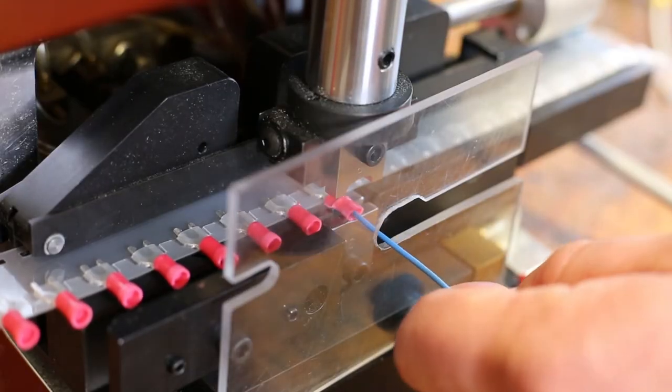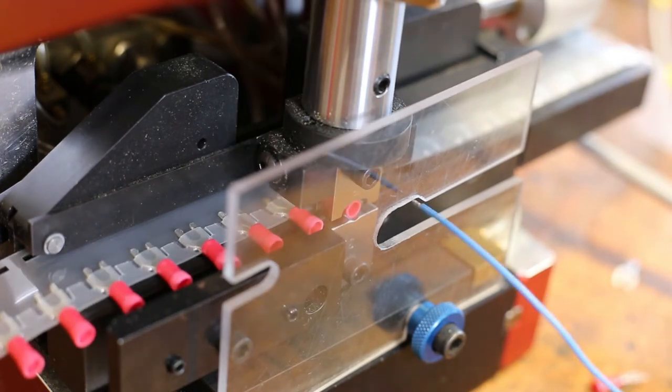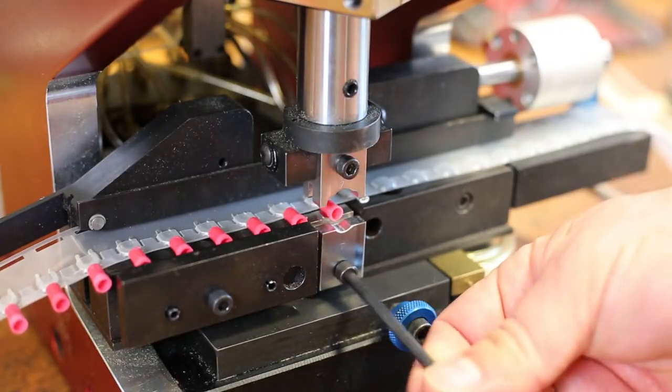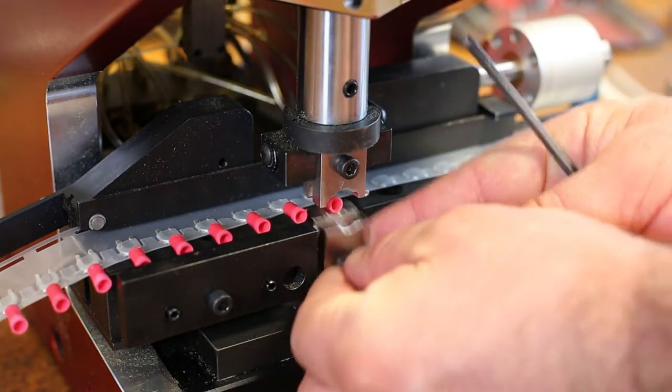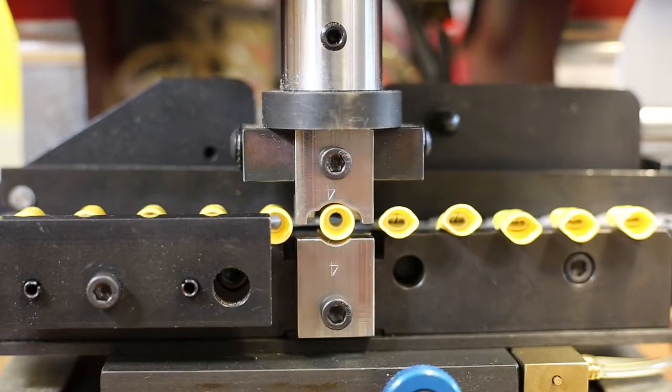The mylar feed will auto-advance after each crimp, and the ram will return to the terminal hold position. The OEM-175-TFM is equipped with a lockout safety mode to ensure you won't injure yourself while changing the dies or mylar feed. The emergency release button also allows you to abort the current crimp operation.